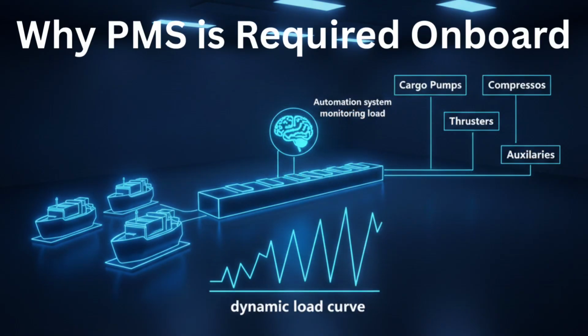Now, let's understand why PMS is absolutely required on board modern ships. Why PMS is required on board ship. Electrical loads are never constant. They vary according to operating conditions, cargo handling, auxiliary machinery, and environmental demands. Cargo pumps, thrusters, refrigeration systems, and air compressors all cause sudden changes in load on the main switchboard.